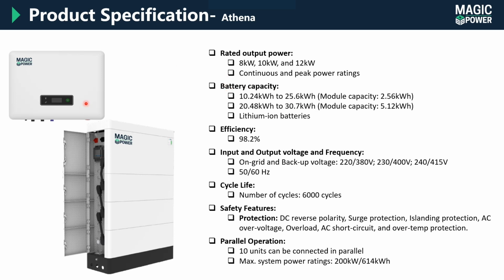System specifications: rated output power 8 kilowatt, 10 and 12 kilowatts, which is a continuous and peak power rating. The battery capacity ranges from 10 to 25 kilowatt hours. In this case, the battery module size is 2.56, and for this one, from 20 kilowatt hour to 30.7 kilowatt hour, the module capacity is 5.12 kilowatt hour. And the technology is again lithium ion batteries.